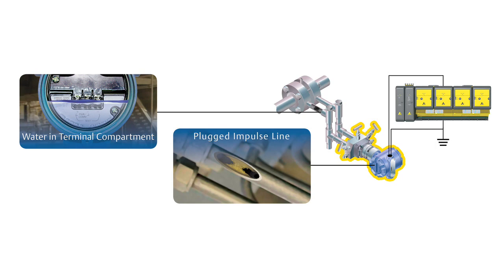When thinking of the sensor subsystem transmitter, it's not just the transmitter. You have to think about the wiring and the power supply — the entire current loop in a 4 to 20 milliamp transmitter. For pressure transmitters, we also have to think about the impulse lines and potential plugging of those lines. Ideally, a pressure transmitter should have automatic diagnostics that include voltage monitoring, compliance voltage monitoring both high and low, and plugged impulse line detection.